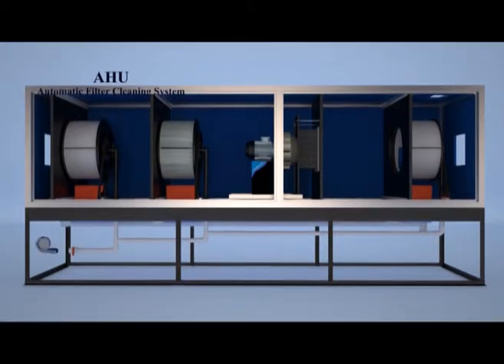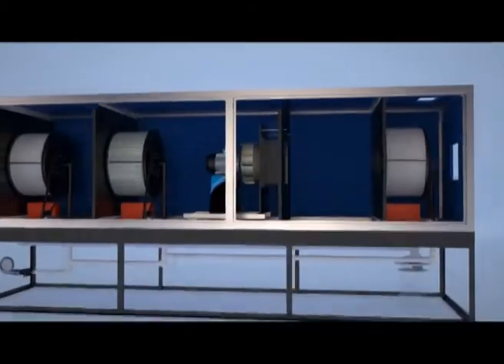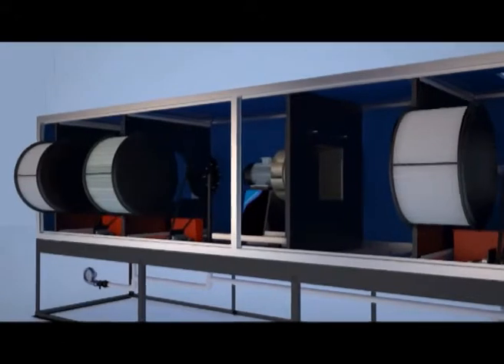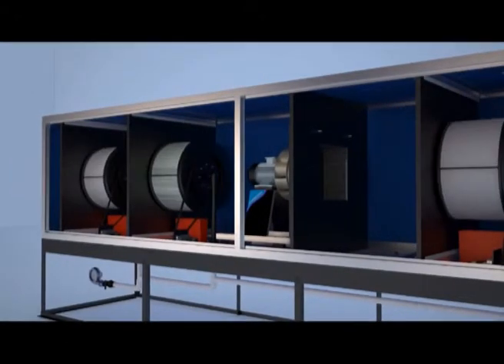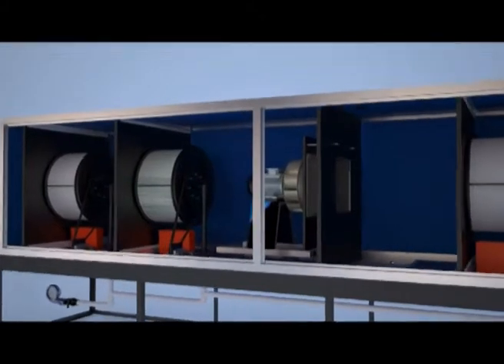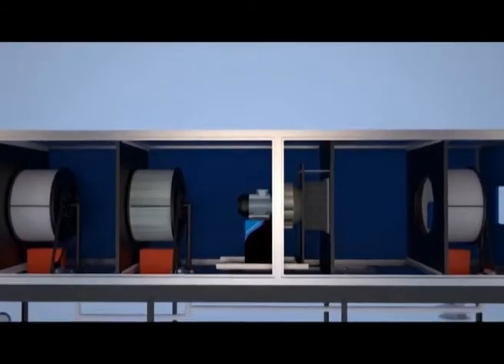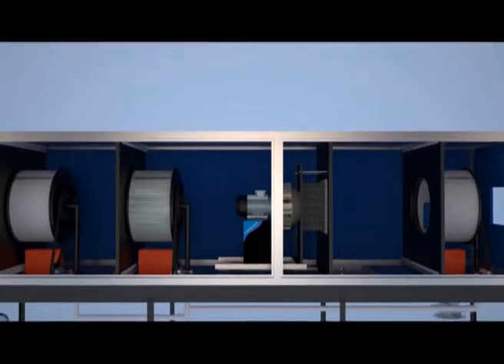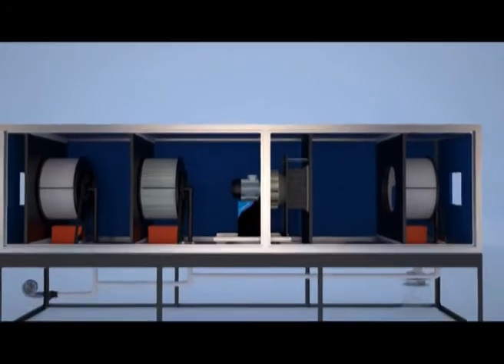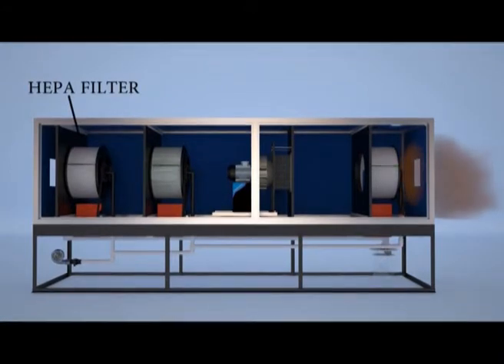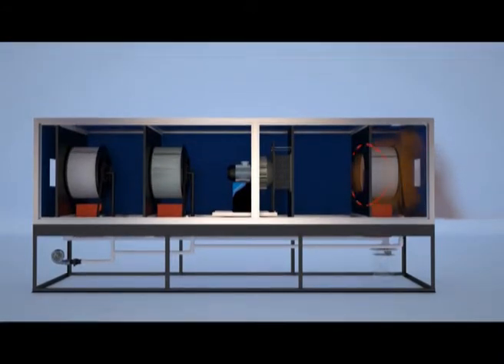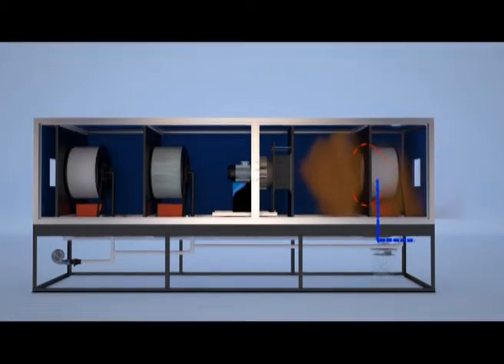How does AHU with automatic filter cleaning system work for you? In our design concept, a number of cylindrical filters can be fitted in the AHU and remain perfectly clean without service by opening the AHU system. They rotate at a slow RPM of about 27 to 30 per hour through a gear motor and timing belt on their axis. The air passes through the outer periphery of the filter to the inside, and the remaining parts of all sides of the filter are closed and sealed. The air passes through only the outer periphery.